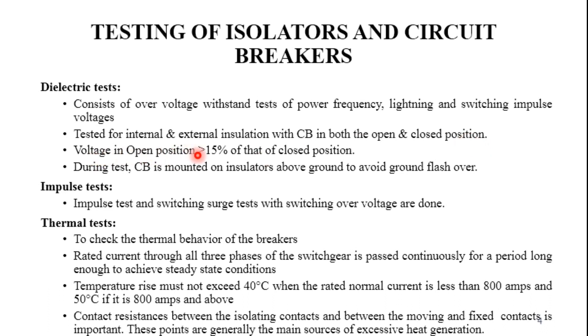Generally, the voltage in the open position is 15% greater than that in the closed position. During the test, the circuit breaker is mounted on insulators above the ground to avoid ground flashover, since there is a possibility of grounding when overvoltage above the rated voltage is applied. For the impulse test, the standard lightning impulse wave shape is used — similar to insulator testing — and switching surge tests with overvoltage are also conducted to assess performance under switching operation overvoltages.